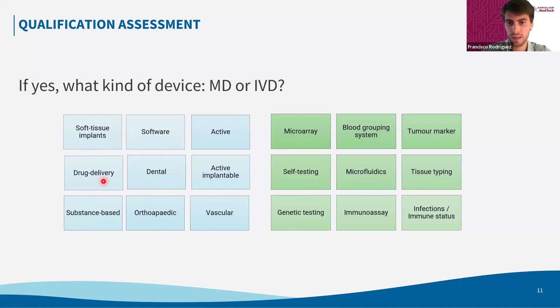Also, the differences between the different kinds of devices will have a consequence in the way we demonstrate the performance, the effectiveness of these devices. So deciding which type of device is a worst case is really important also when conducting the medical device qualification. Here you have the definition provided by the legal framework specifically.